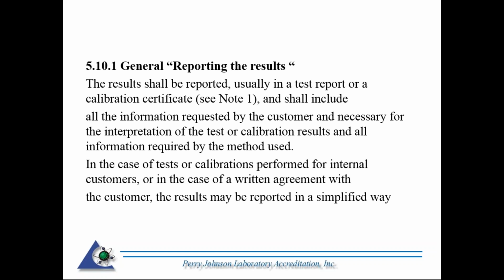In the case of test or calibrations performed for internal customers, or in the case of a written agreement with a customer, the results may be reported in a simplified way. So what this is saying, you may have an external customer that just, for internal purposes, or even an external customer, for whatever reason, they want reported just whether or not their artifact or sample was within specifications or out of specifications.